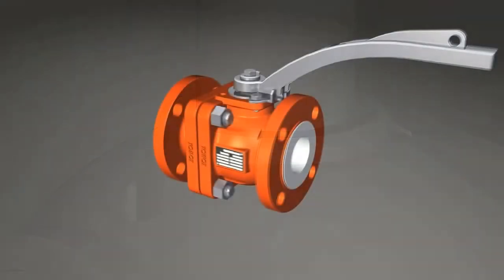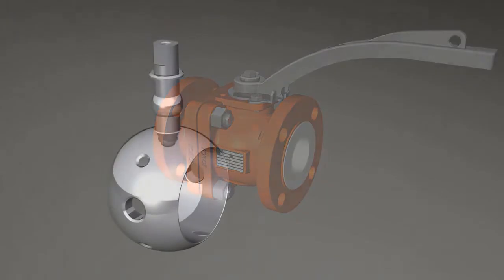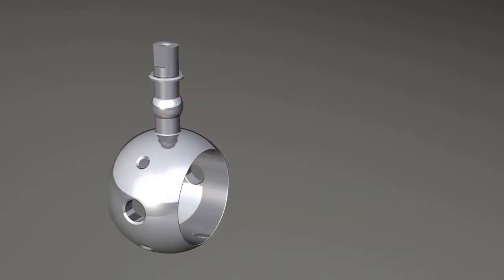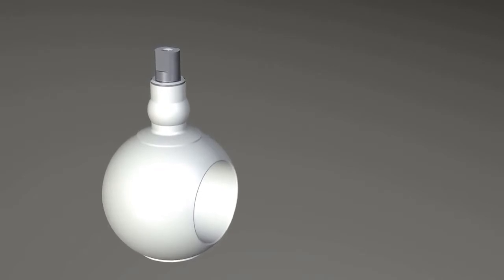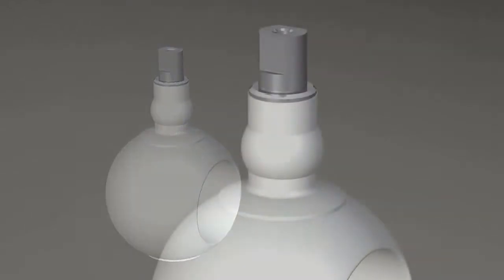This can lead to potential leakage. With our new design, the metallic core of the ball and stem is manufactured as a single piece and then lined with PFA. Consequently, this kind of wear cannot occur and the danger of safety-related incidents caused by internal corrosion is substantially reduced.